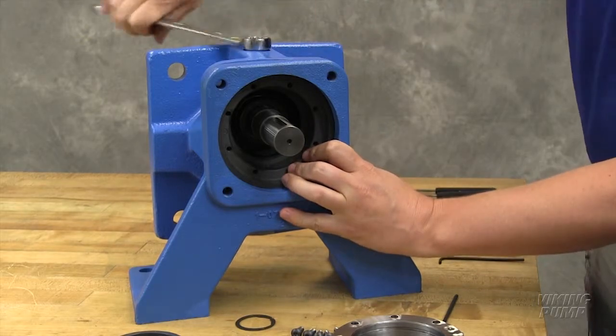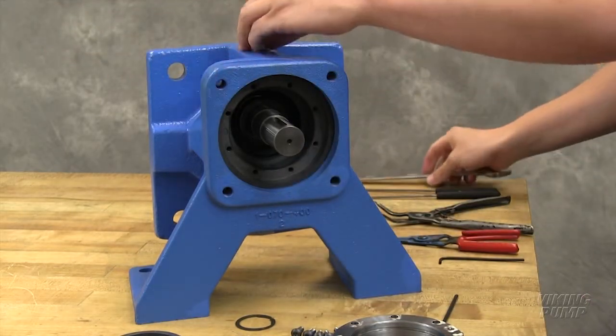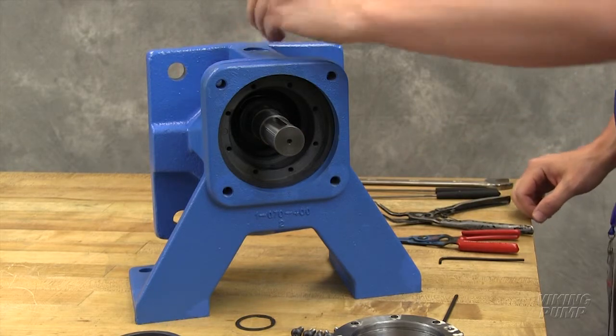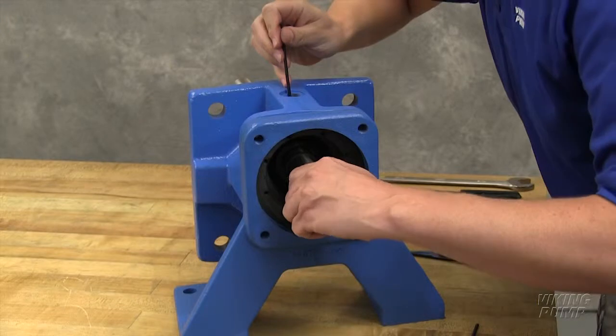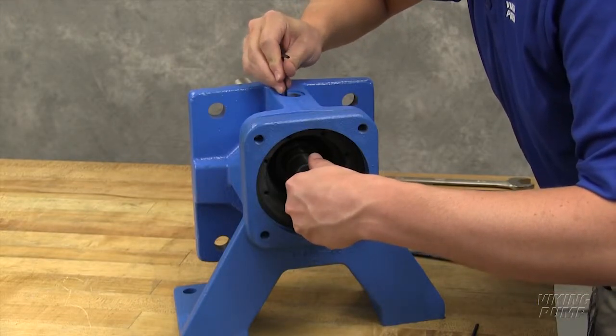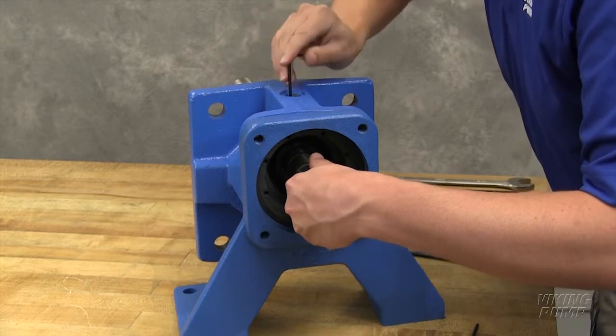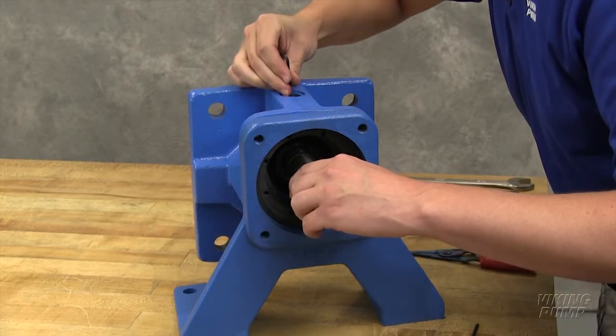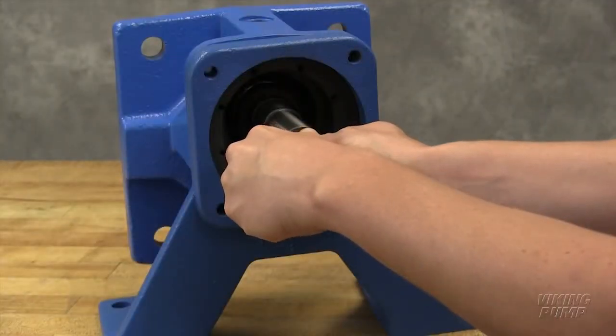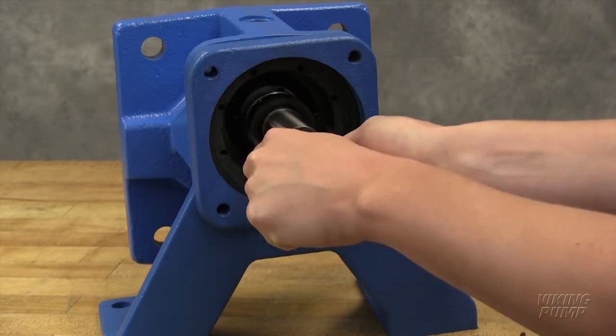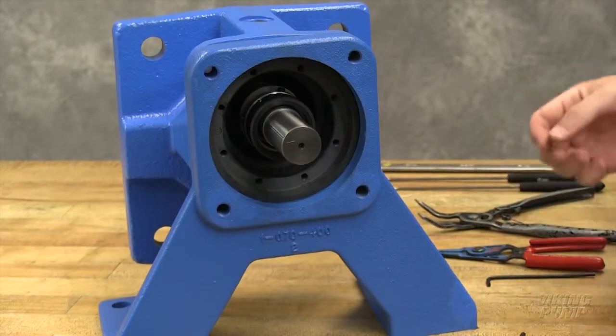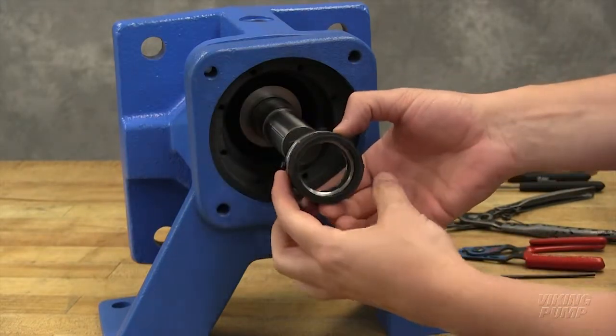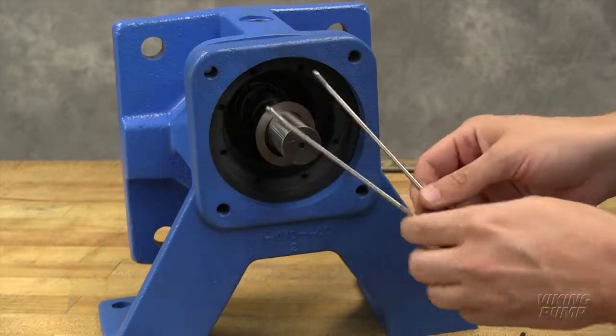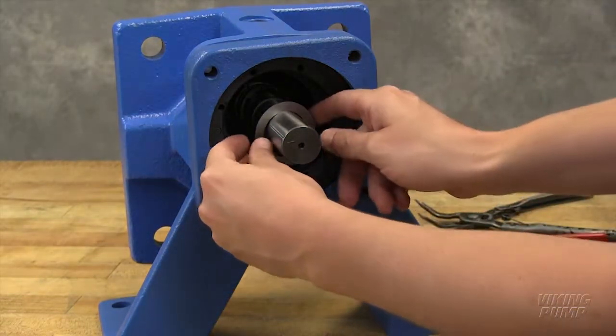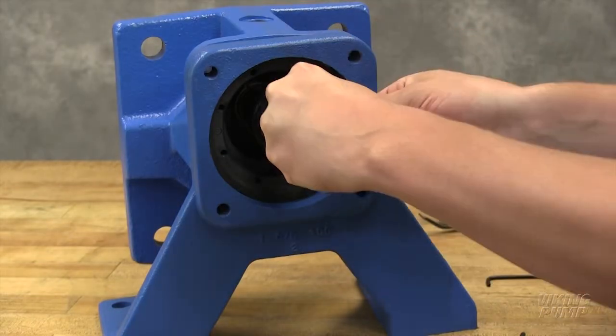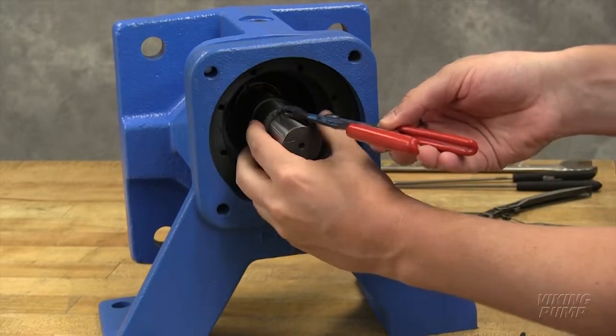Remove the SAE O-ring plug on the top of the pump bracket to obtain access to the set screws on the rotating element of the mechanical seal. Loosen the set screws on the mechanical seal. These set screws are 90 degrees apart. Rotate the pump shaft to access each set screw. Use a pair of picks to reach into the seal chamber to hook and pull the mechanical seal out. Remove the seal washer and shim. Use the snap ring pliers to remove the retaining ring on the shaft.